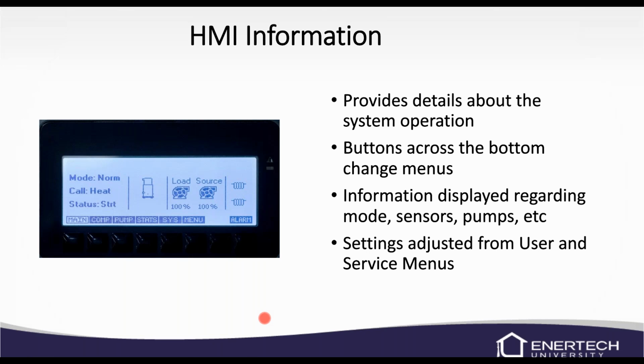A little bit of the human-machine interface information. Again, this is the standard screen that you will see when you come up to the unit and push a button so the light comes on. Basically, it provides details about the system operation. There's buttons, they're kind of hard to see in this picture, but they're kind of shiny underneath it. If you want to get to the compressor menu here, you press the button that's underneath it. Same thing with the pumps and the stats, system menu, and the alarm. It's basically just going to show your information displayed regarding the mode, the status, the pump speeds, things like that.